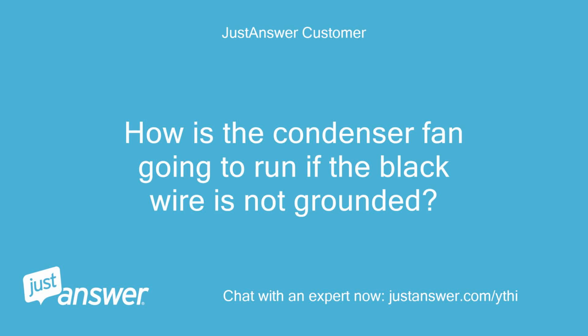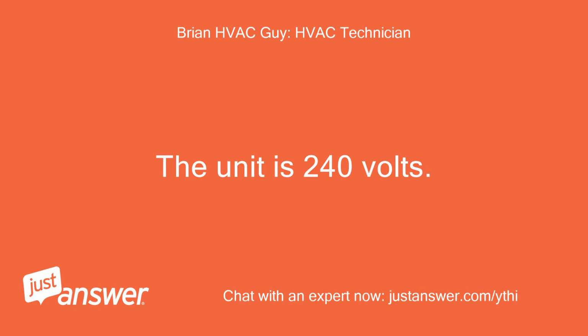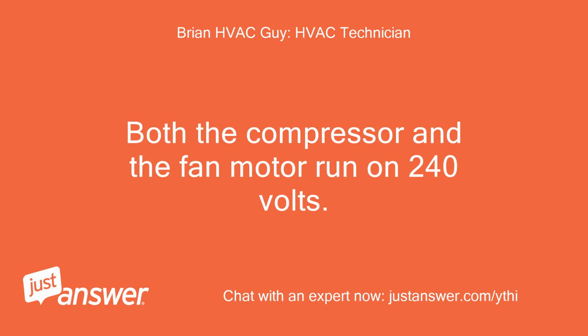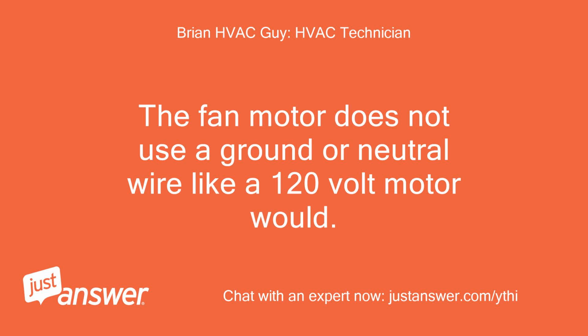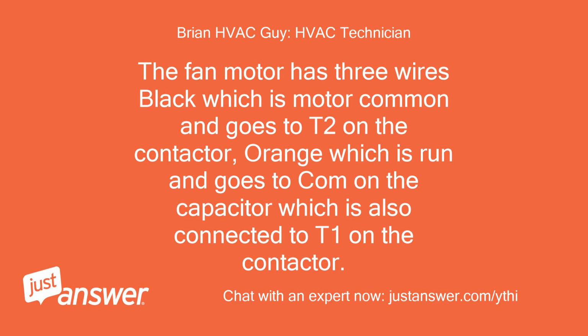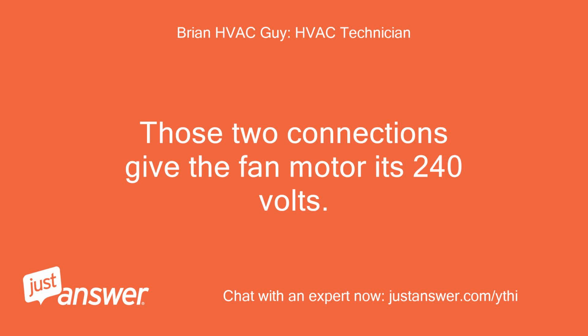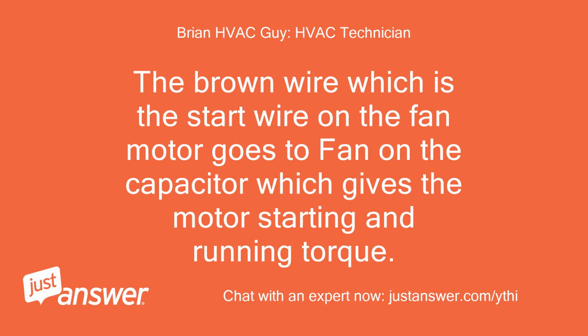How is the condenser fan going to run if the black wire is not grounded? The unit is 240 volts. Both the compressor and the fan motor run on 240 volts. The fan motor does not use a ground or neutral wire like a 120 volt motor would. The fan motor has 3 wires: black, which is motor common and goes to T2 on the contactor, orange, which is run and goes to COM on the capacitor, which is also connected to T1 on the contactor. Those 2 connections give the fan motor its 240 volts. The brown wire, which is the start wire on the fan motor, goes to fan on the capacitor, which gives the motor starting and running torque.